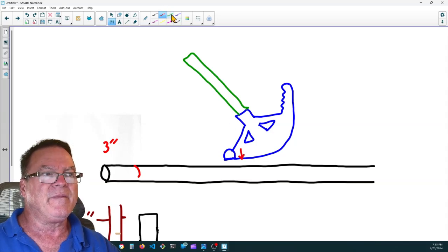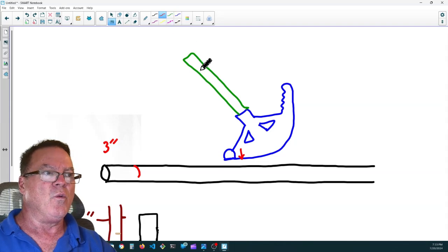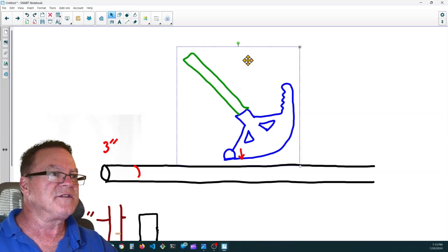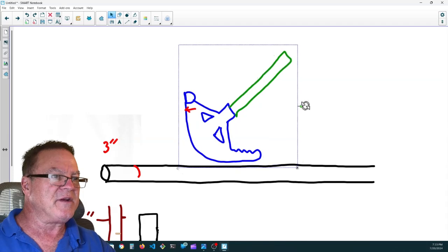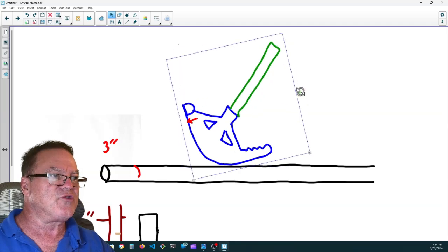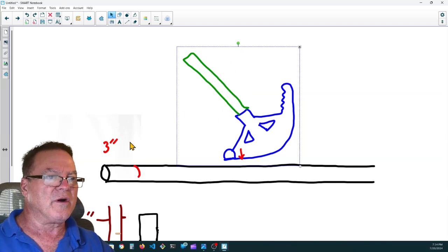And usually for a 1/2 inch EMT bender, the take up will be 5 inches. What take up means is that when you've bent a 90-degree bend, and this bender is sitting in this orientation, this arrow is going to be 5 inches off the ground. So if you want an 8-inch 90, you're going to subtract the take up of the bender. You'll subtract that 5 inches, and you'll mark the pipe at 3 inches.